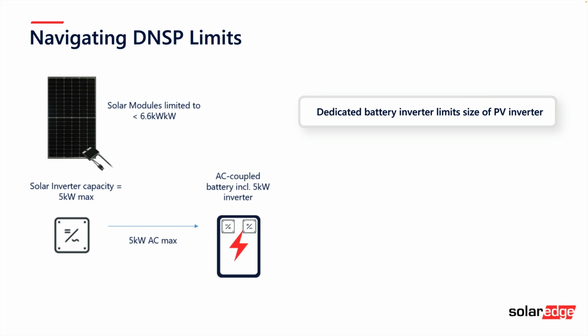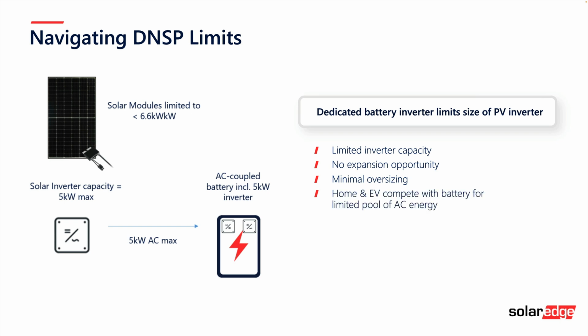Looking at a typical single phase site, you may be limited in your inverter capacity if adding an AC coupled battery, because you won't have the expansion opportunities we have with SolarEdge. You'll have a 5 kilowatt inverter for the battery, which limits you to a 5 kilowatt inverter for the solar. This minimizes your oversizing abilities, meaning your home, electric car, and all your loads need to compete to fill from that limited 5 kilowatt output pool of AC.